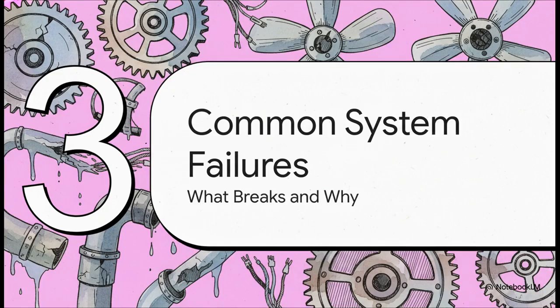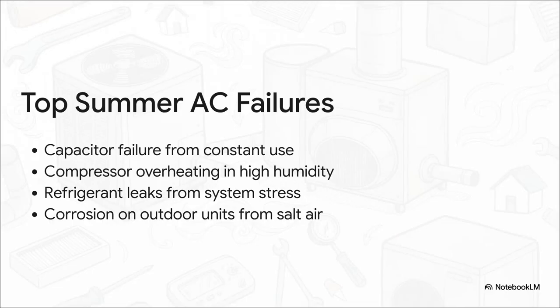So with all that pressure from the outside world, what's actually breaking on the inside? Let's get into the mechanical parts most likely to give up under that pressure. In summer, the heat and humidity are brutal. Capacitors, the little parts that give motors a jolt to start, get fried from being overworked. The compressor, basically the heart of the whole system, can easily overheat. And that salt in the air literally eats away at the outdoor unit. Every one of these failures is a direct result of the local climate.